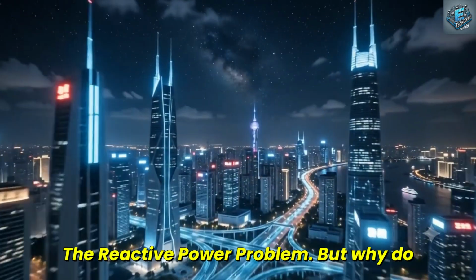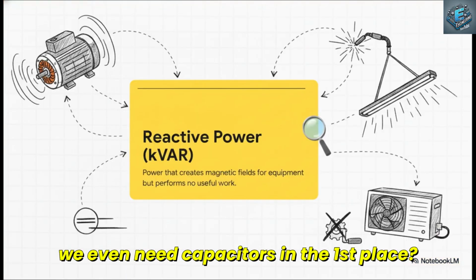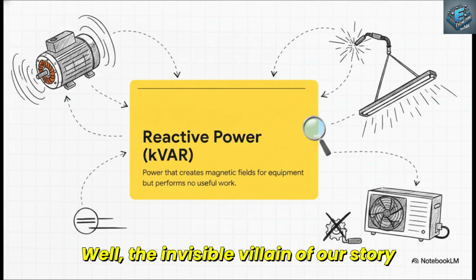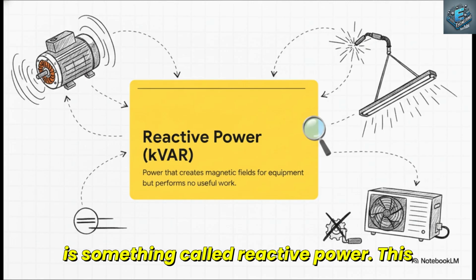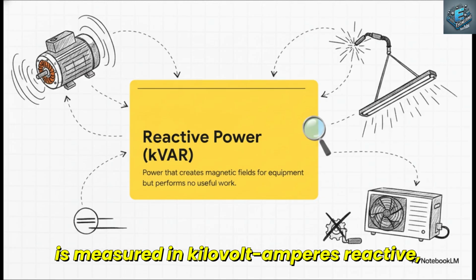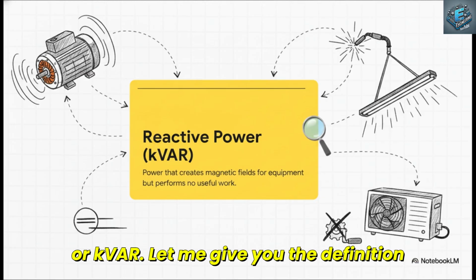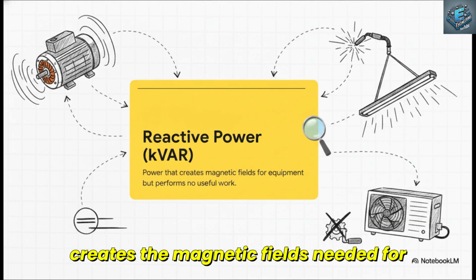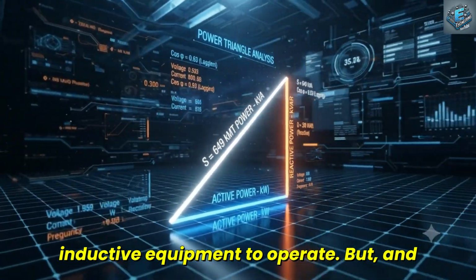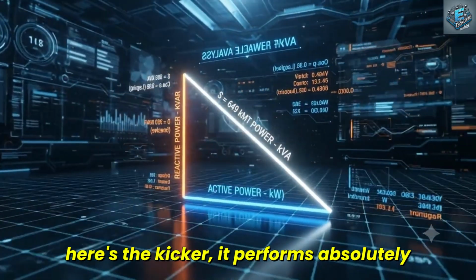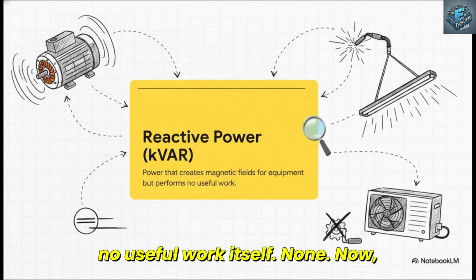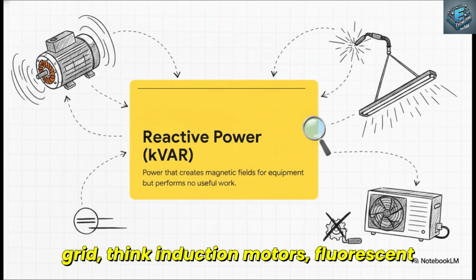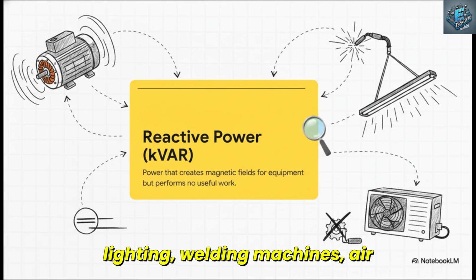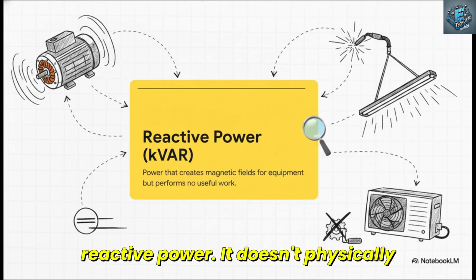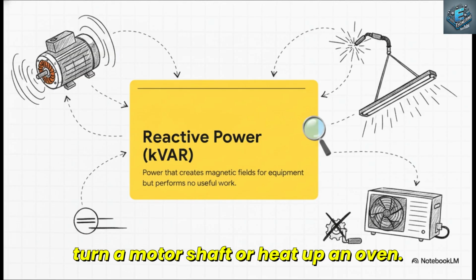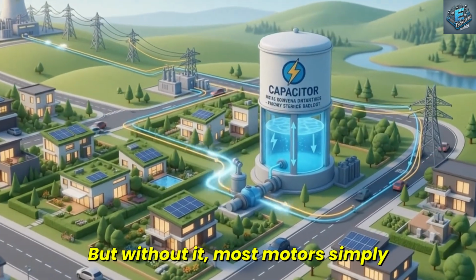Section 2: The reactive power problem. But why do we even need capacitors in the first place? The invisible villain of our story is something called reactive power, measured in kilovolt amperes reactive, or kVAR. Let me give you the definition clearly: reactive power is power that creates the magnetic fields needed for inductive equipment to operate. But here's the kicker: it performs absolutely no useful work itself. None. Many common electrical devices on the grid—think induction motors, fluorescent lighting, welding machines, air conditioners—absolutely need this reactive power. It doesn't physically turn a motor shaft or heat up an oven, but without it, most industrial motors simply wouldn't run.